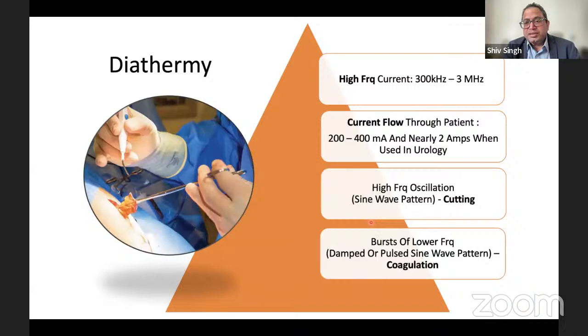It is 200 to 400 milliamps and nearly 2 amps when used in urology. So if you were to have such current flow at 50 hertz, this will cause microshock, cardiac arrest, and death. So why doesn't it actually cause a shock? Even though such a huge amount of current is flowing through the body, why is it not causing any harm to the patients? Well, it is causing harm. It can cause burns. And that's what the diathermy and coagulation does.